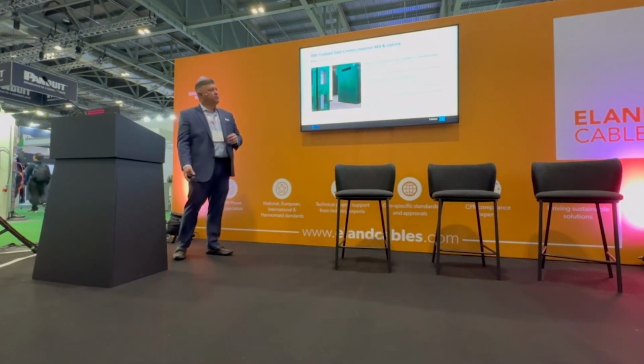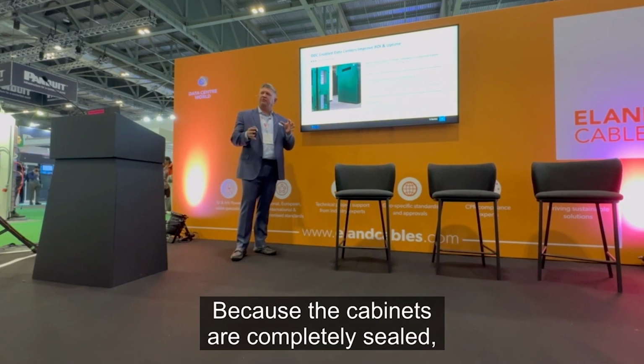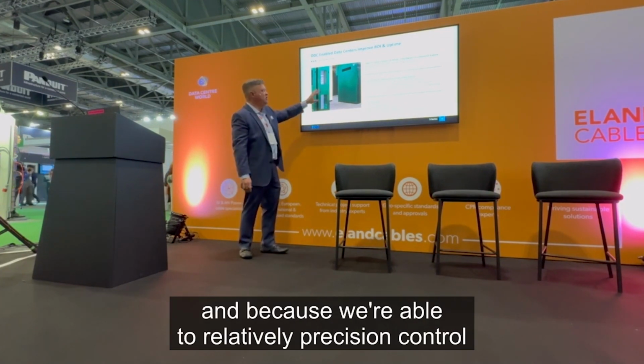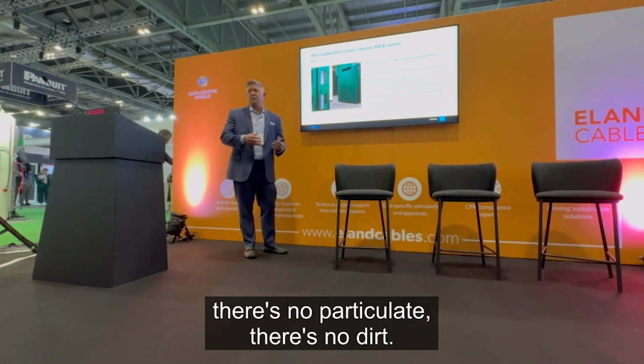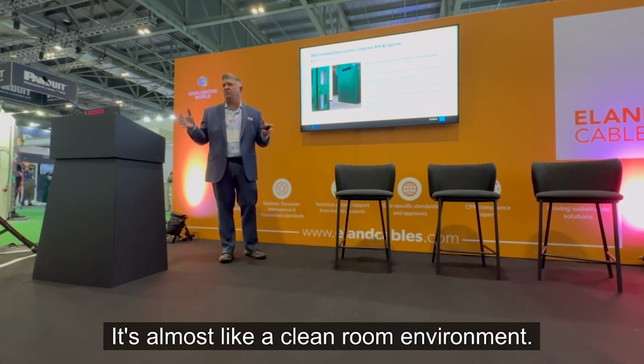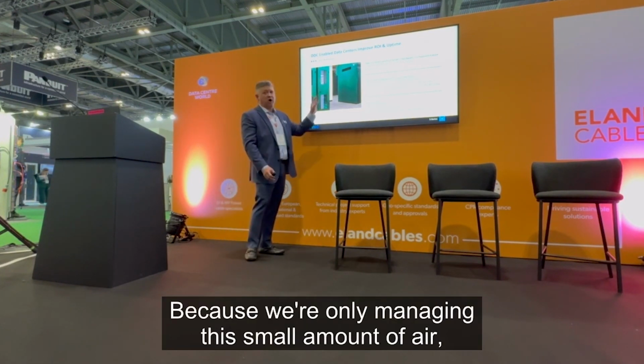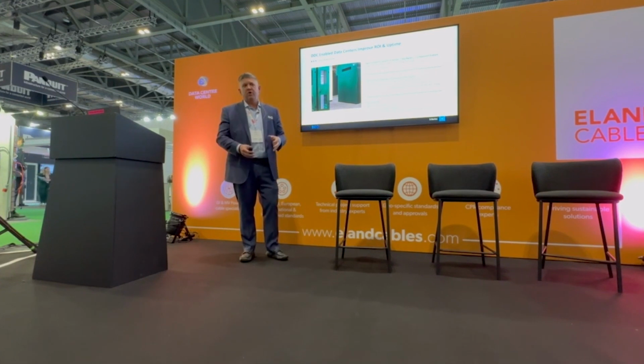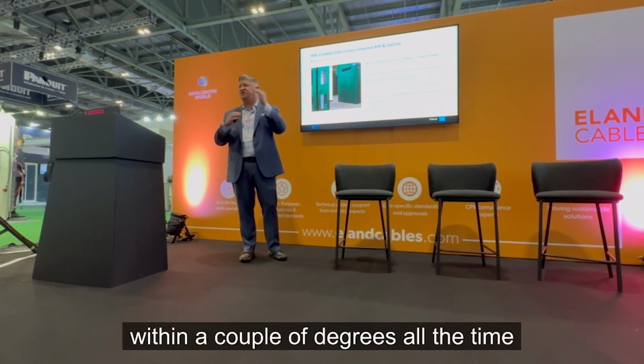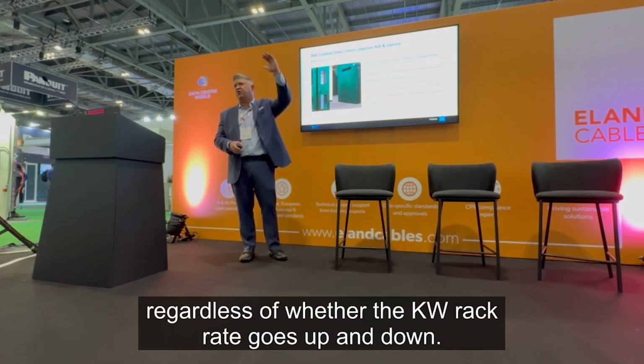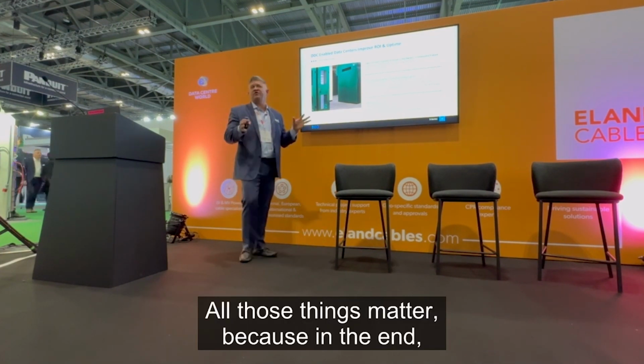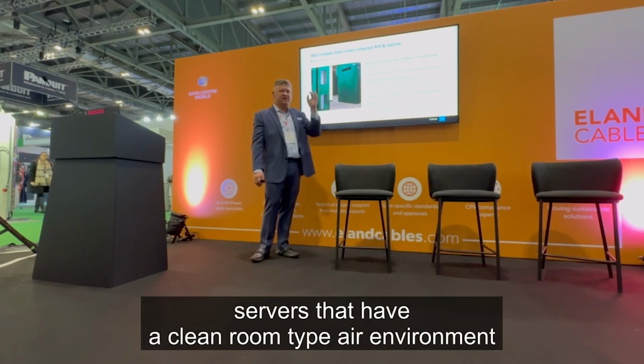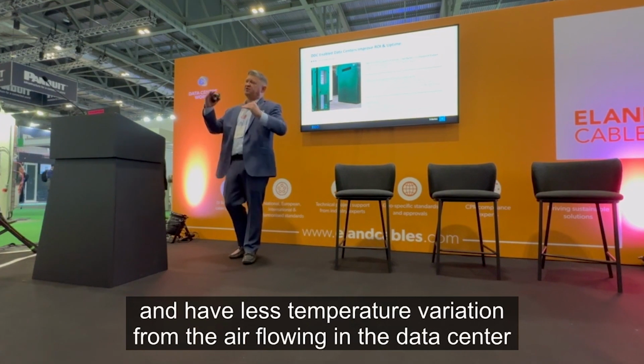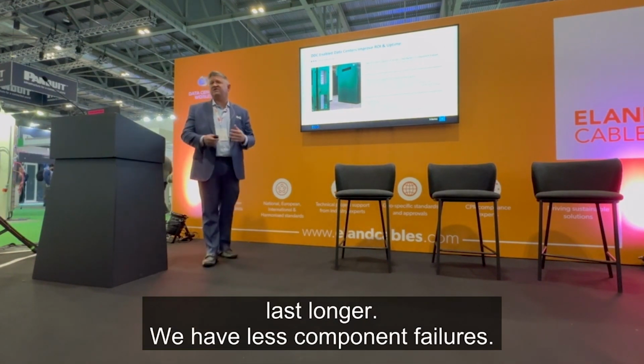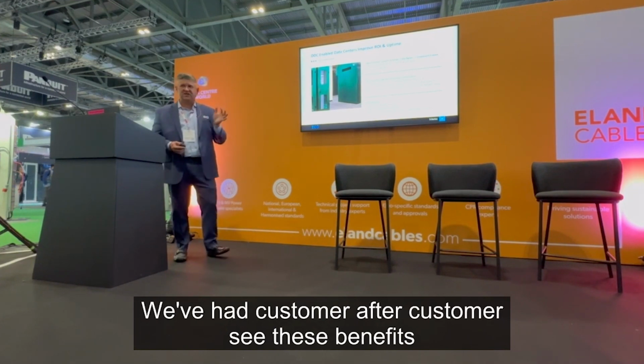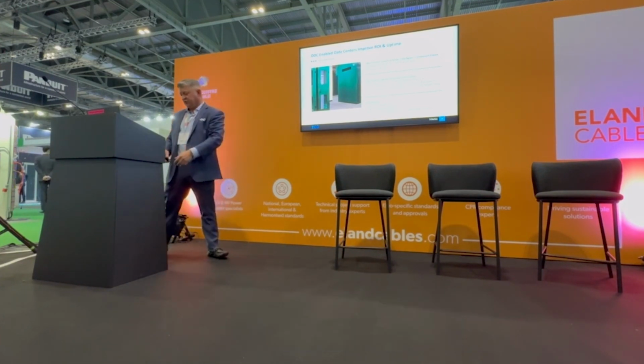Because the cabinets are completely sealed, we're able to precisely control the amount of airflow in the front end. There's no particulate, there's no dirt. It's almost like a clean room environment. And because we're only managing this small amount of air, not the entire data center envelope, we're able to control the temperature variation within a couple of degrees all the time, regardless of whether the kW rack rate goes up and down. All those things matter because, in the end, servers that have a clean room type air environment and have less temperature variation from the airflow in the data center last longer. We have fewer component failures. We've had customer after customer see these benefits over the last 13 years the platform's been deployed.